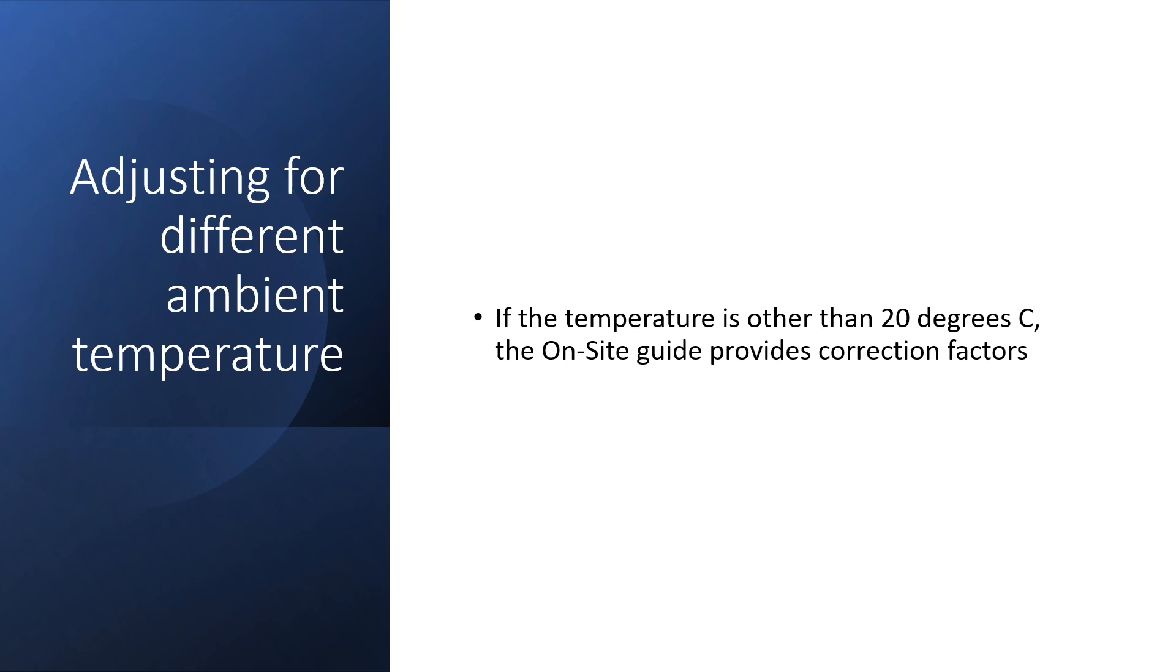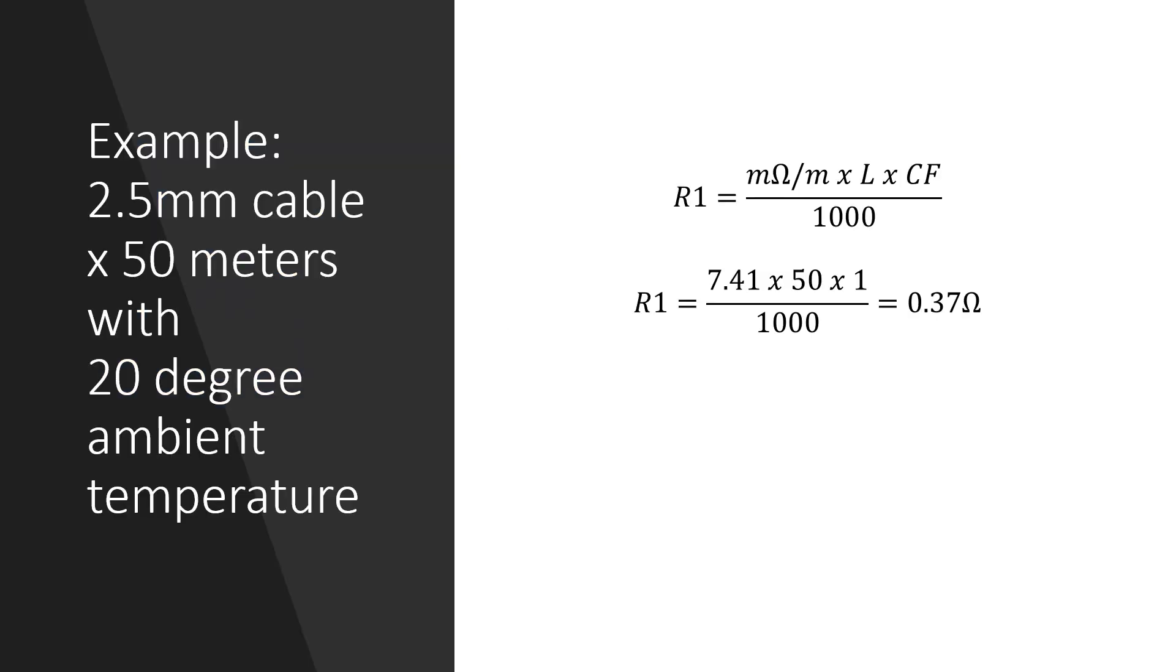So if we assume the ambient temperature is 20 degrees then we can simply work out the end-to-end value by multiplying the length by the value for milliohms per meter and then dividing by 1000.